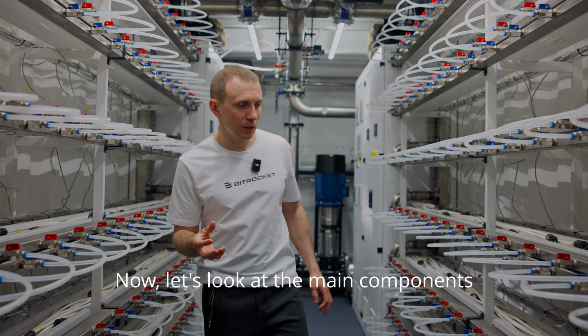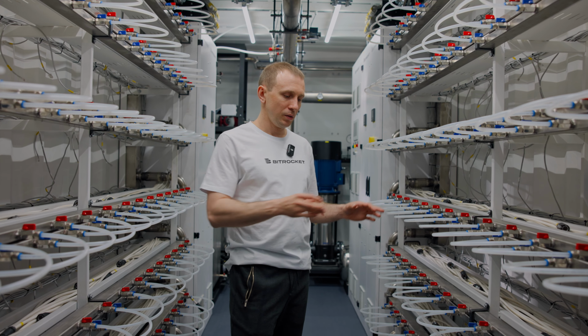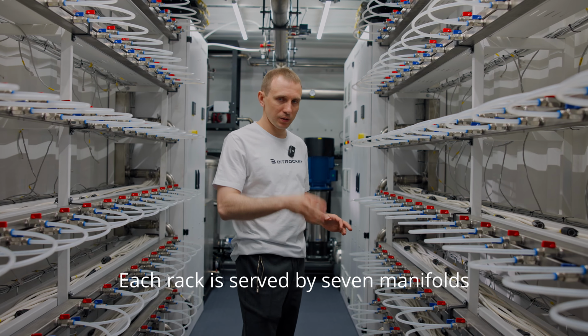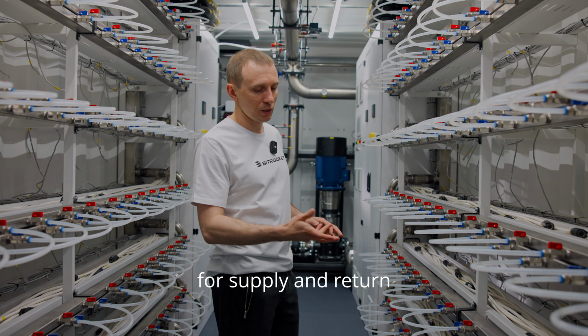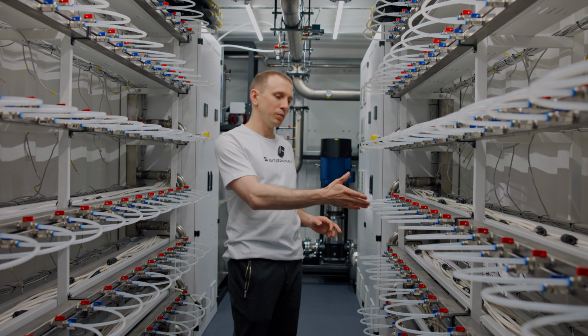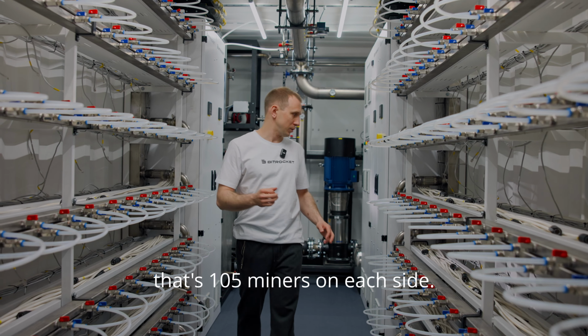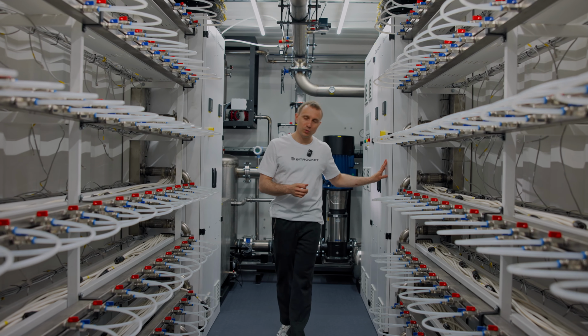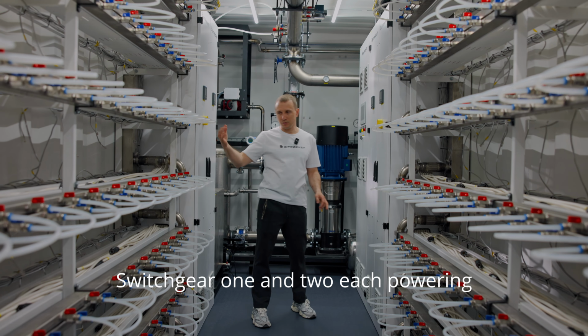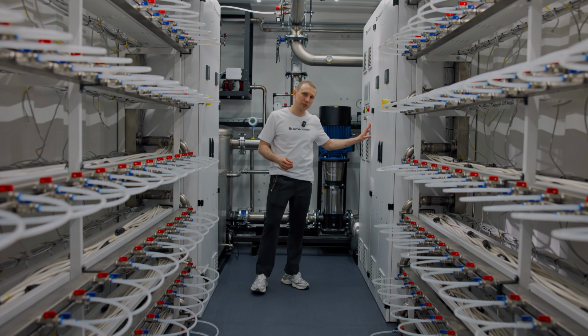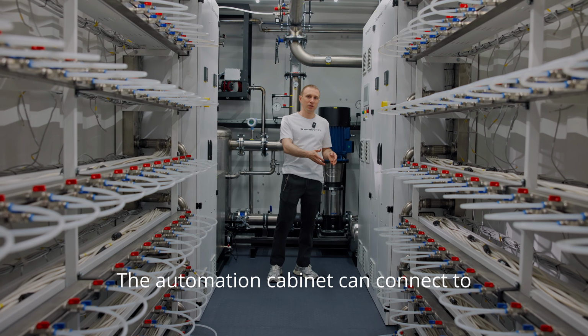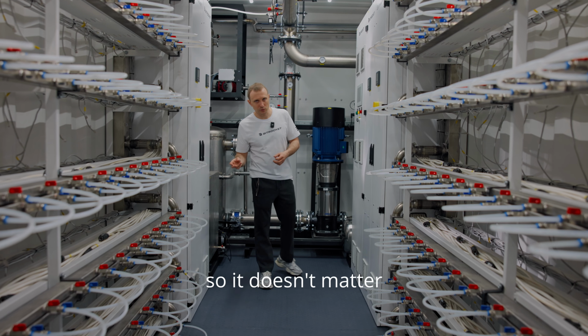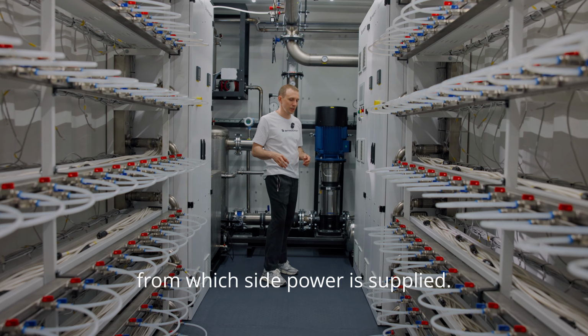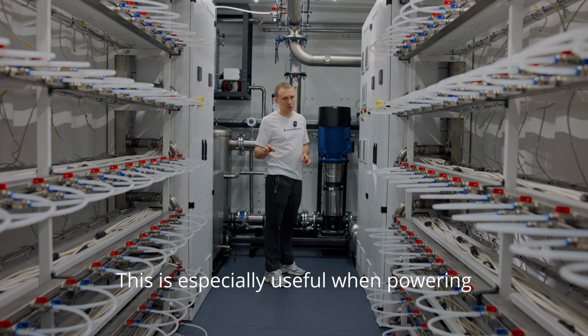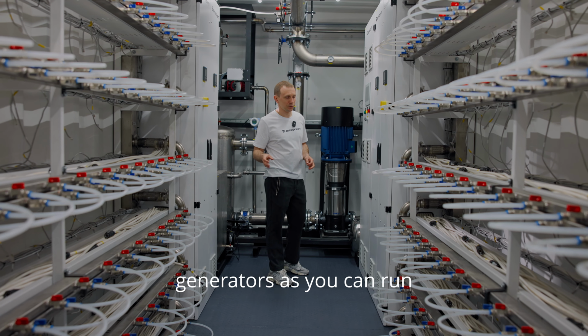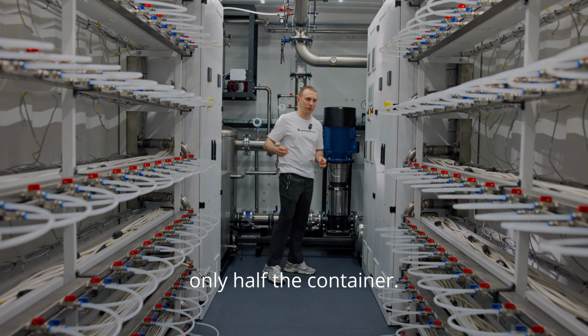Now, let's look at the main components inside the container. Each rack is served by 7 manifolds for supply and return, with 15 miners in each. That's 105 miners on each side. Switchgears. Switchgear 1 and 2, each powering one half of the container. The automation cabinet can connect to either of the switchgears, so it doesn't matter from which side power is supplied. This is especially useful when powering the container from generators, as you can run only half the container.